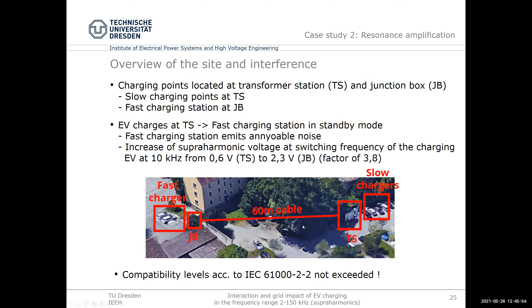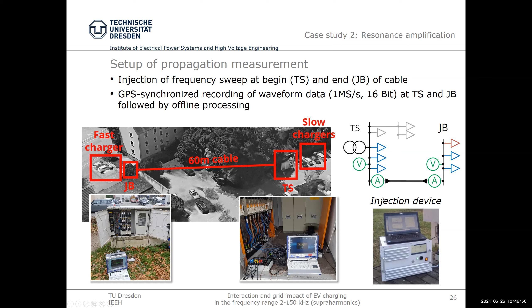How did we do it? We took an injection device able to sweep the frequency range up to 250 kilohertz, injecting current. We connected it first at the transformer station and did synchronized measurements of voltages and currents at the junction box as well as the transformer station. Then we switched the injection device to the junction box, injecting there, and again looked at voltages and currents at the two measurement points, transformer station and junction box.